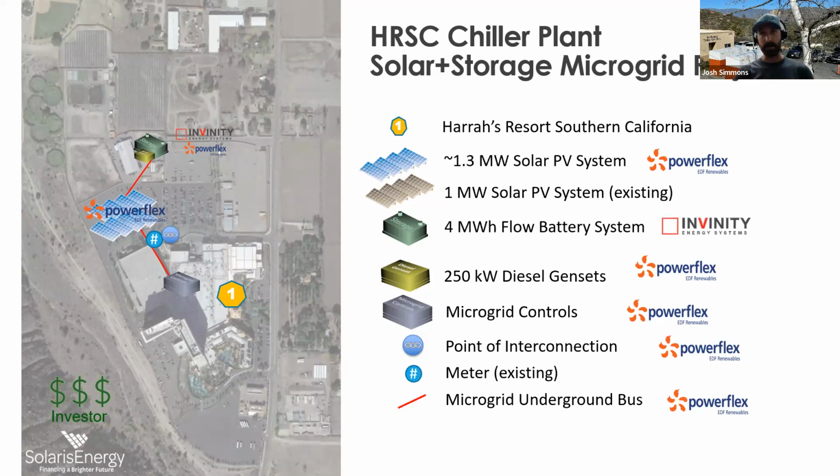The backup generator here, that's actually not a backup generator. It's a black start generator. The flow battery cannot come online by itself during an outage, so the diesel generator kicks on to get the flow battery going, and then it'll kick off.